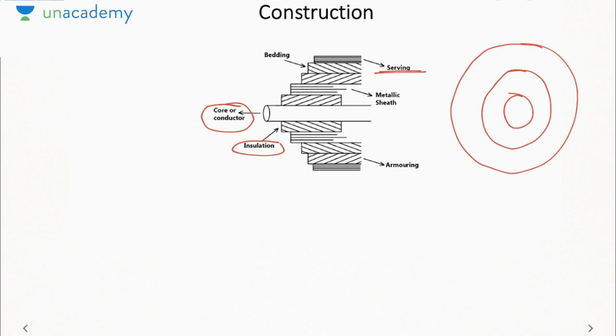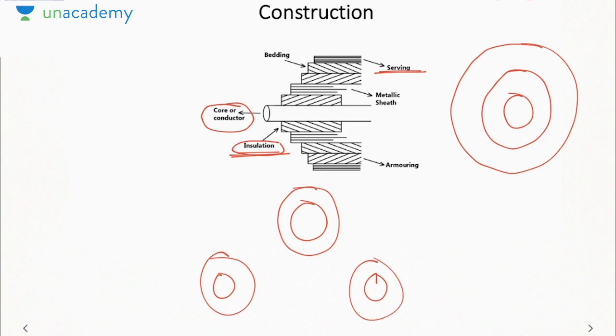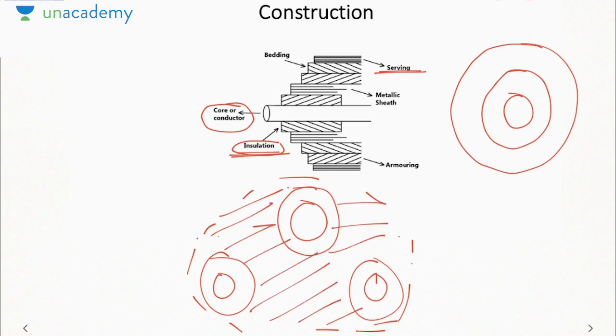Now, whenever there is more than one conductor inside a cable, the insulating layer will be different for each conductor, but the rest of the outside layers will be the same. Like I just told you, suppose this is one conductor, second conductor, third conductor, and then there will be insulation, but outside the insulation all the layers will be common for all 3 conductors. That is why, if we incorporate more than one conductor in a single cable, cost is saved, because the outer protective layers are the same for all 3 conductors. That is why we have a lesser cost if we use a multi-core cable.